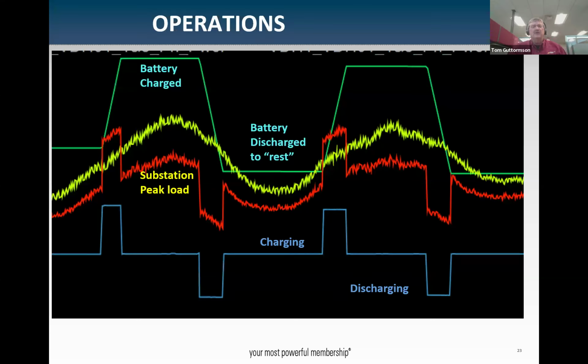So this is a little profile of what this looks like. This bottom blue line is energy flow to the battery. When it's up like this, we're charging the battery, and the battery is at rest, then we discharge the battery, and it's at rest again. The red line is the substation transformer load that the battery is connected to. In the middle, the yellow line is the other substation transformer, and the red one is the one it's connected to, where you can see the peak load is.